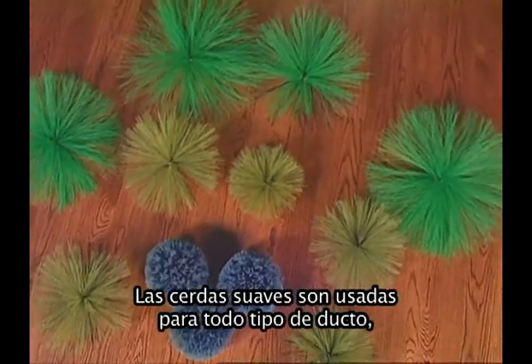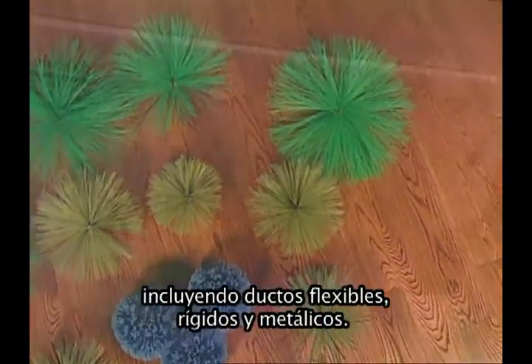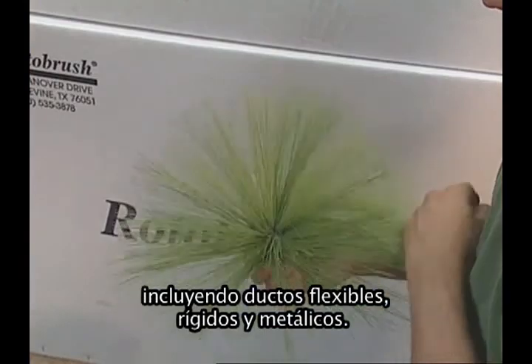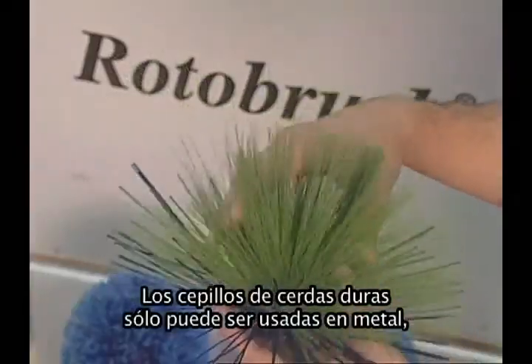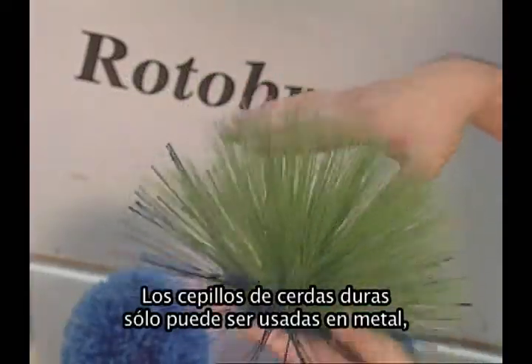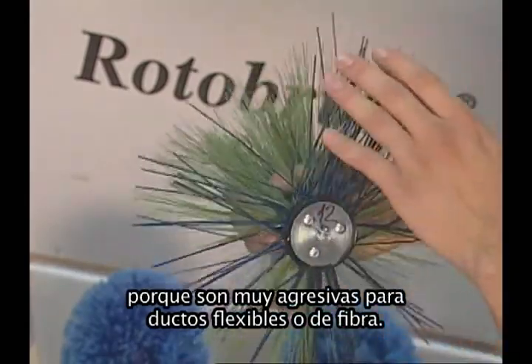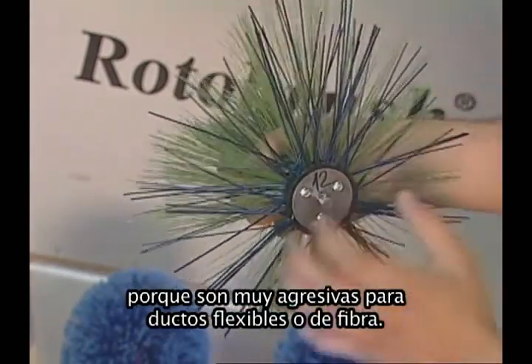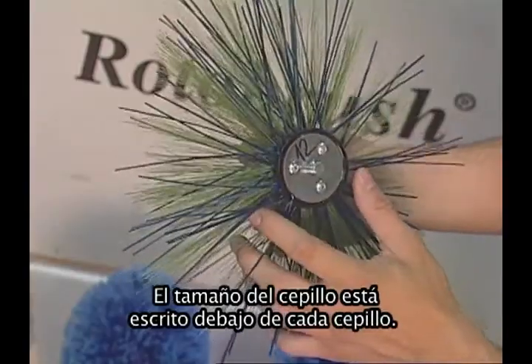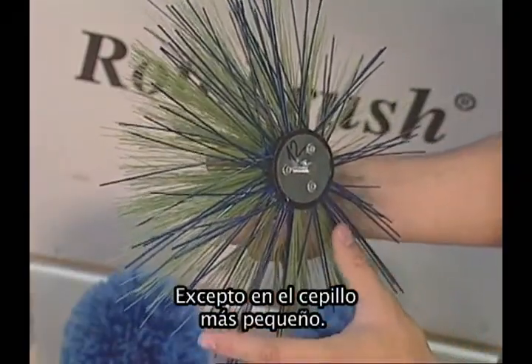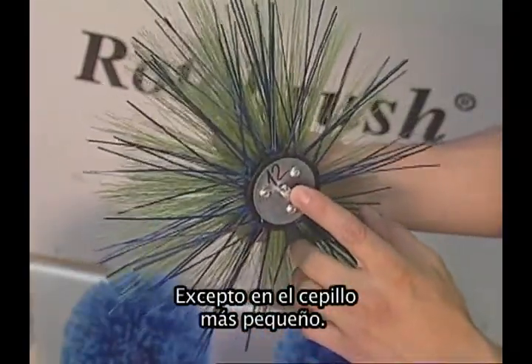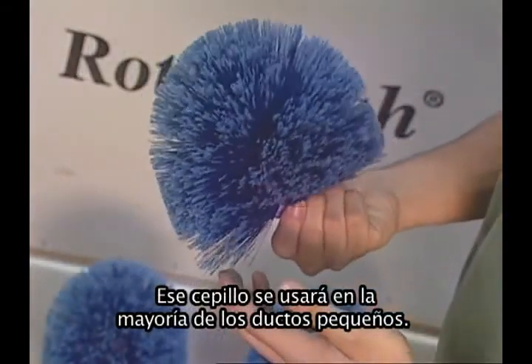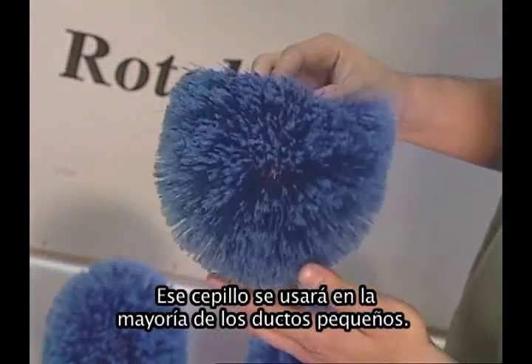Soft brushes are used for all types of ductwork, including flex duct, ductboard, and sheet metal ducts. The stiff bristle brushes are only to be used on sheet metal ductwork because they are too aggressive for flex duct or fiberboard ducts. The brush size is written on the bottom of each brush hub, with the exception of the small 8-inch brush. You will use the 8-inch brush to clean the majority of smaller supply air ducts.